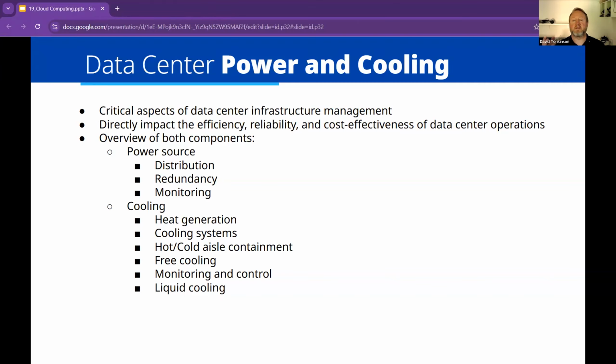Now, if I want more redundancy, what happens if one of those diesel generators fails? Well, hold on, do I cut off some of my systems? So what I have is an N+1, which is the number of generators, plus 1 spare, just in case. And we could do N+2 if we're more and more secure.